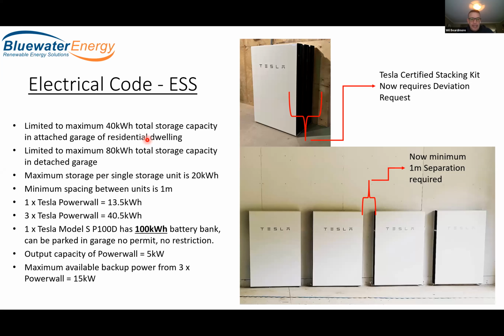We can go up to 80 kilowatt hours in a detached garage or a detached separate structure that is not a dwelling unit. The maximum storage per single storage unit is 20 kilowatt hours. And the minimum spacing between energy storage units is 1 meter.